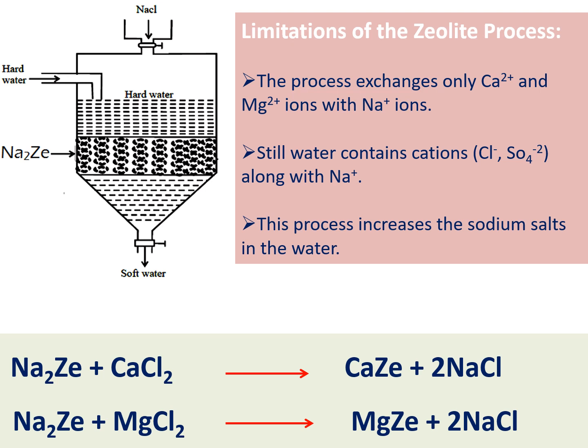In the last class we discussed briefly about the zeolite process. Zeolites are called Na₂Ze; they have a porous texture and two sodium ions on each molecule, loosely bounded on the surface. These sodium ions can be replaced by Ca²⁺ and Mg²⁺ present in the hard water. So we can replace all cations in the hard water by Na⁺ ions, but still the water contains anions like chloride, sulfate, and bicarbonate ions.